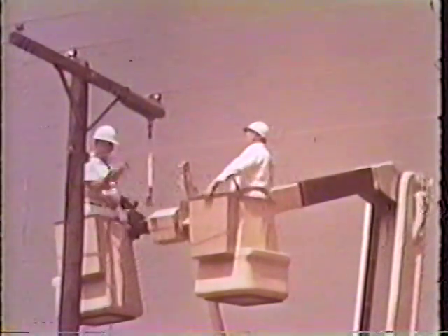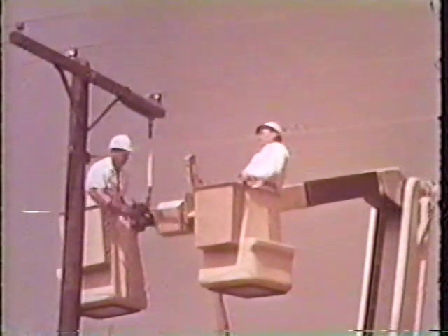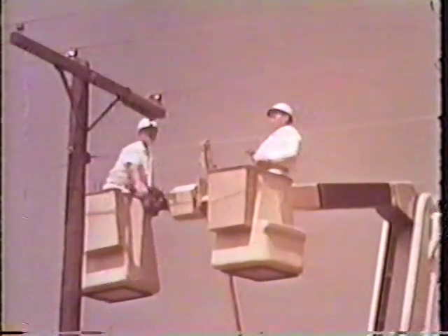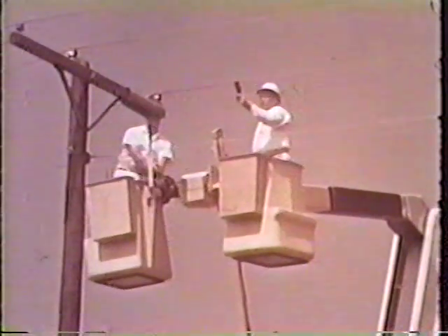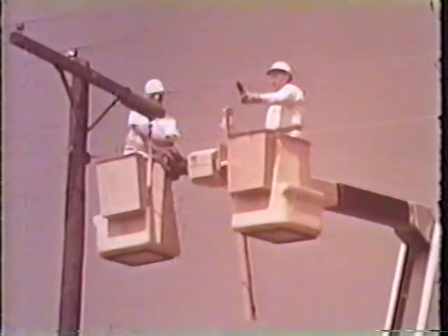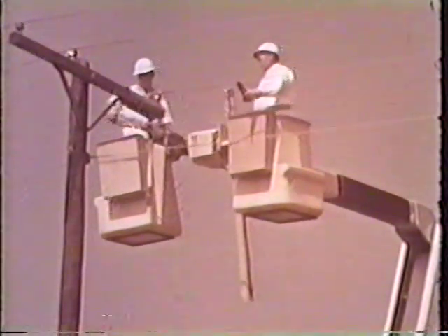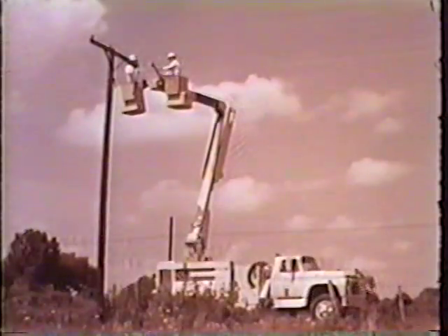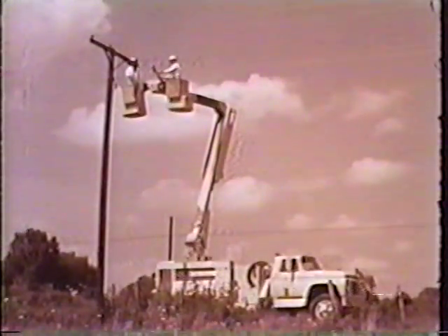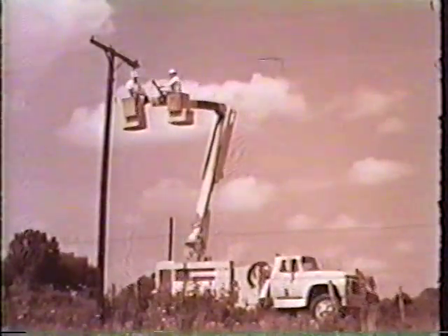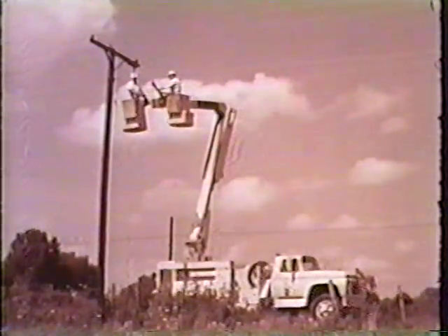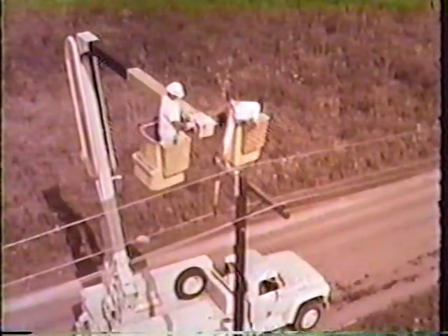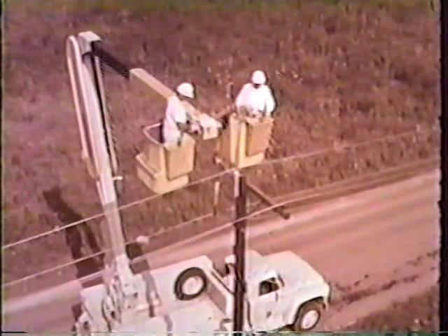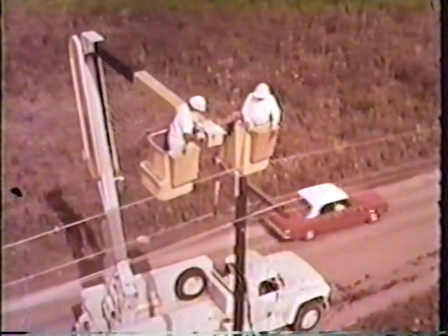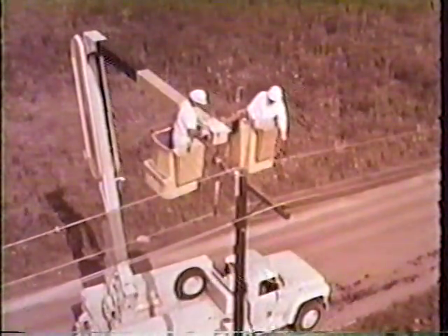Here's how a bare-hand crew changes out a broken ridge pin insulator on a 12.5 kV pole on a typical rural distribution line. A link stick is attached to the cross arm and an insulated barrier slipped under the near insulator. Barriers are used wherever necessary up to voltages around 69 kV, where clearances are no problem. The conductor is then removed from the insulator and lowered in the pivot boom to the support of the link stick. With the conductor out of the way, the men return to the top of the pole, move into the center phase, the bucket straddling the cross arm, and clip on to the conductor.